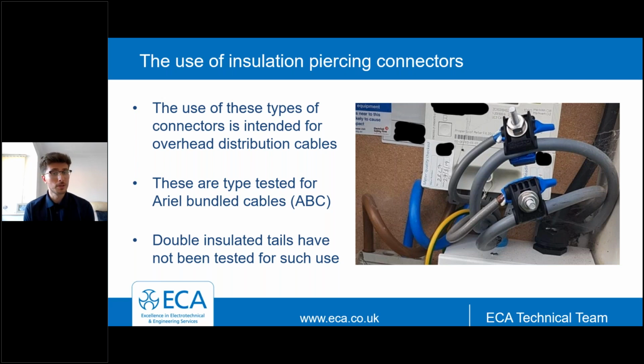And again, this is probably looking at when adding EV charge points to existing installations. There can be difficulties in where to locate this equipment. And again, I've been referring to this pre-work survey. You need to assess this before carrying the works out. The use of insulation piercing connectors is intended for overhead distribution cables. This is what these connectors are designed for. They are type tested for aerial bundled cables.